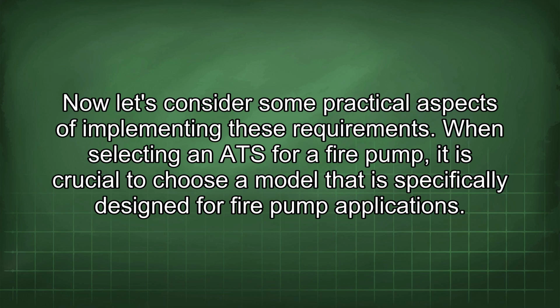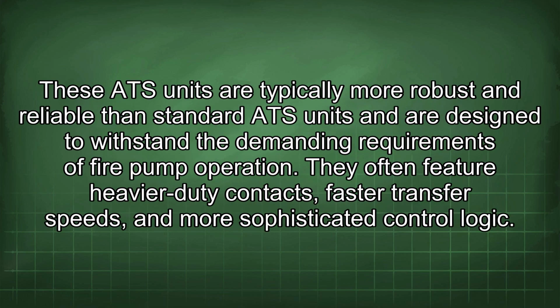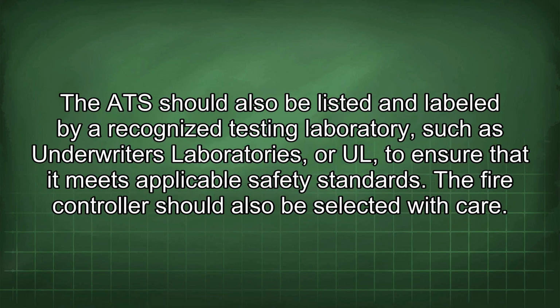When selecting an ATS for a fire pump, it is crucial to choose a model that is specifically designed for fire pump application. These ATS units are typically more robust and reliable than standard ATS units and are designed to withstand the demanding requirements of fire pump operation. They often feature heavy-duty contacts, faster transfer speeds, and more sophisticated control logic. The ATS should also be listed and labeled by a recognized testing laboratory, such as Underwriters Laboratories, to ensure that it meets applicable safety standards.